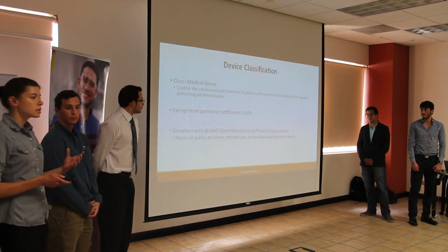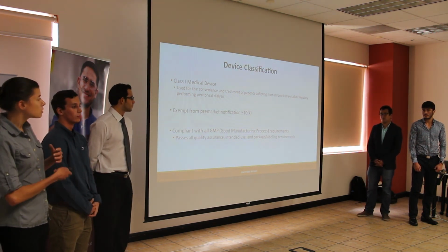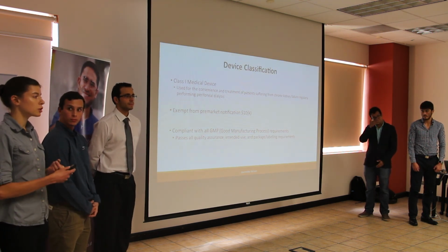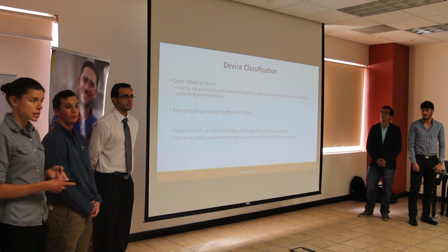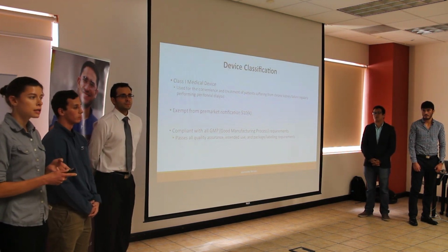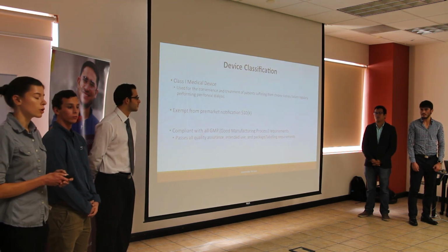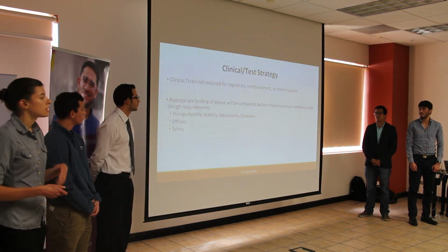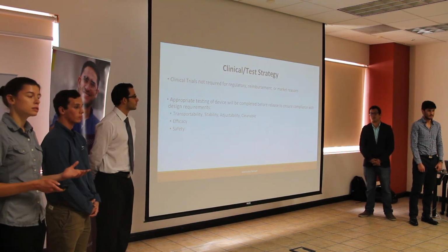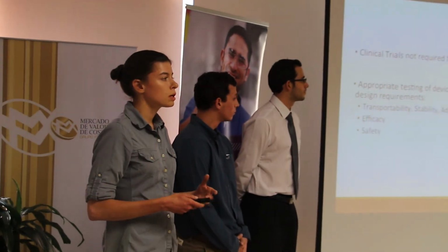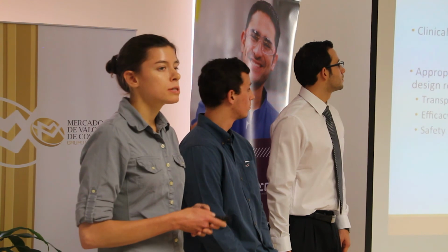That being said, we still need to comply with good manufacturing practice requirements. We need to make sure that it keeps up a good quality, that it meets all standards, that it's labeled appropriately, and that people know how to use it, which goes into the training that we mentioned before. Like I said, because it is a Class 1 medical device, it does not need clinical trials to proceed to market. We do want to make sure that it acts as it's required to, though, so we will be testing it before we give it to the customers.